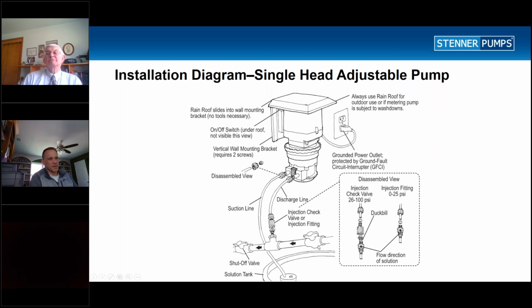We also recommend mounting the injector in a T between the 2 shutoff valves, and this just makes it easy to replace the tube and to service the pump because you're able to relieve pressure on both ends. And then we also talked about the assembly of the connecting nuts. The only thing that you should use to tighten the connecting nuts on the pump tubes and also the injector fitting is just your fingers, and you don't have to get crazy with it.